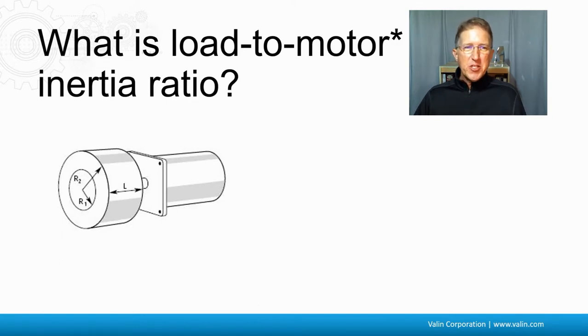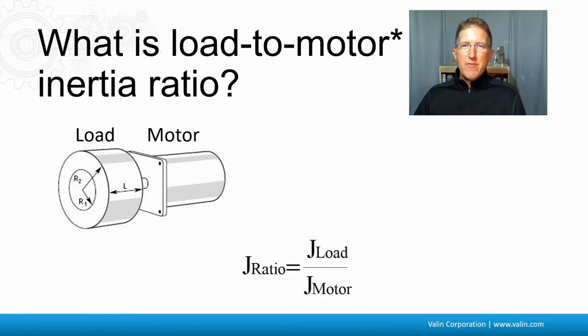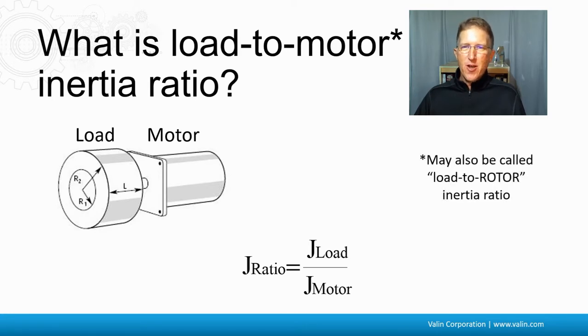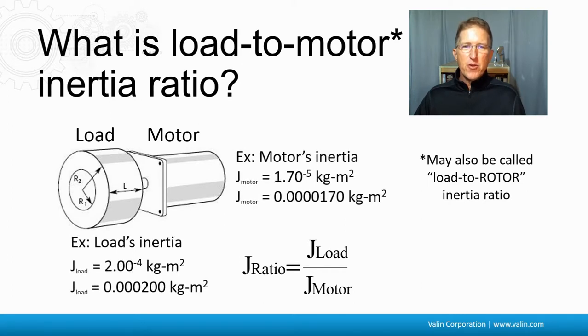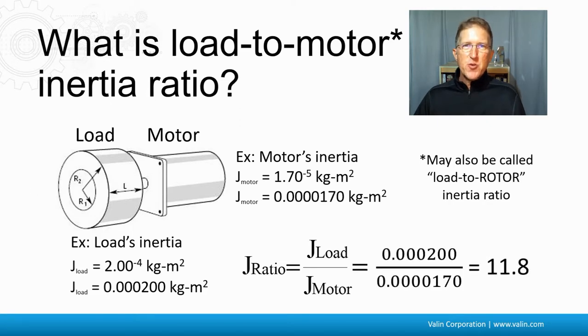So what is the load-to-motor inertia ratio? If you have a motor with a load on it, you have the ratio of the load inertia over the motor inertia. Note that this is sometimes called the load-to-rotor inertia ratio, because the rotor inside the motor is what actually spins. For example, with some typical values, that ratio might come out to 11.8. J is the standard terminology for inertia.